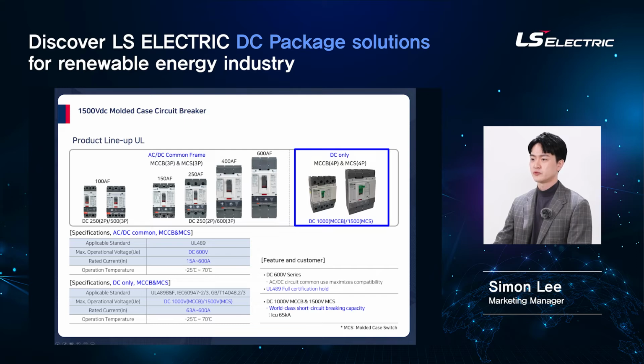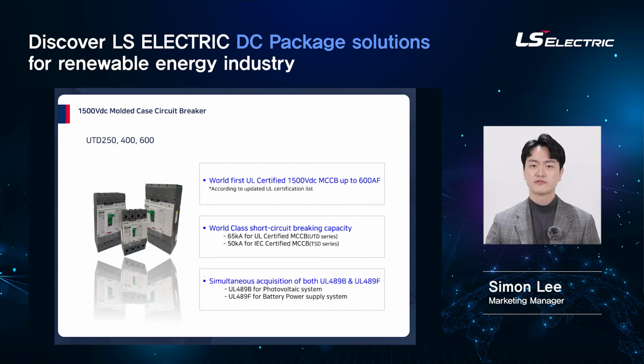Aside from previous UL breakers compatible both with AC and DC, our new DC breaker up to 1500 DC volts mentioned earlier are launched this year. In this slide, I would like to emphasize those main features of our 1500 DC volts UL MCCB. It is world first UL certified DC MCCB up to 600 amps at 1500 DC volts. And high short circuit breaking is guaranteed, which is 65 kA for UL and 50 kA for IEC. Acquisition of both UL489B and UL489F is also a main feature I would like to emphasize.